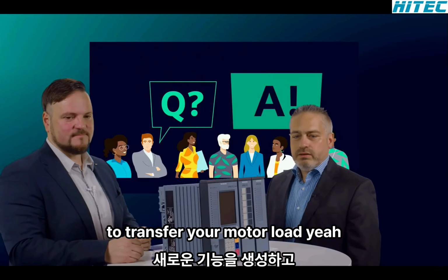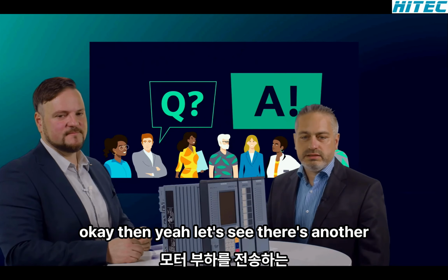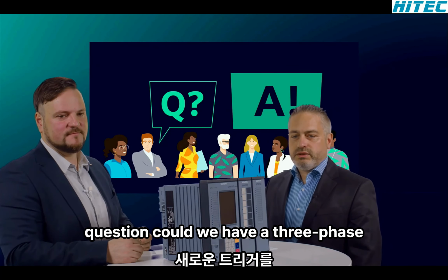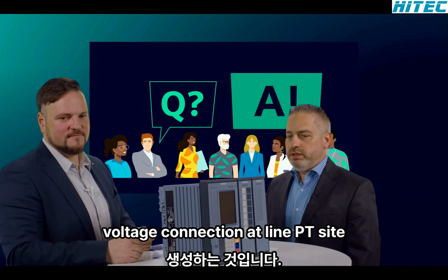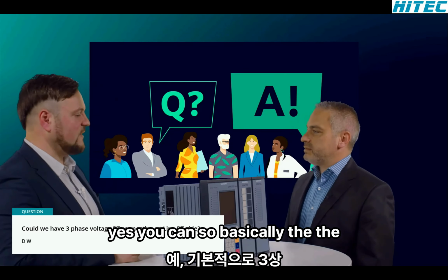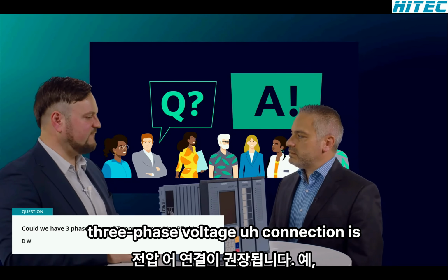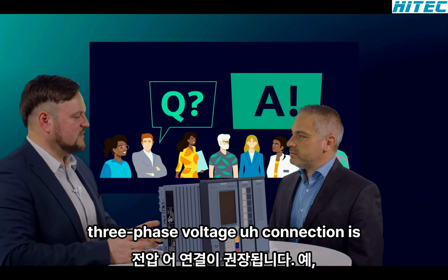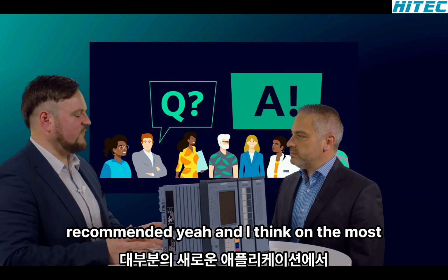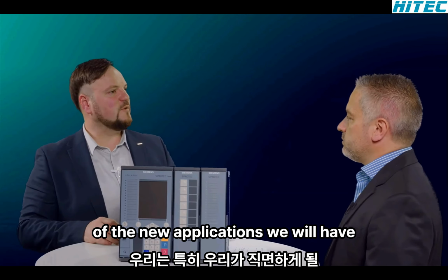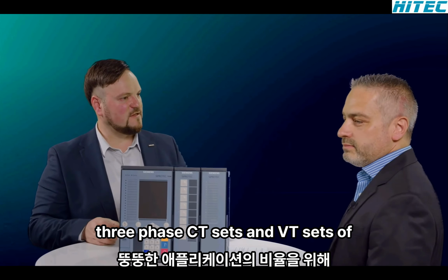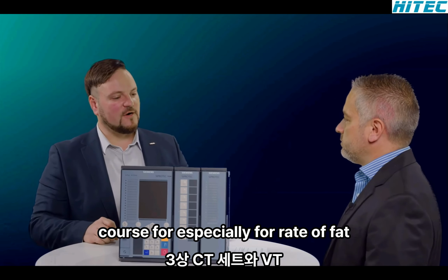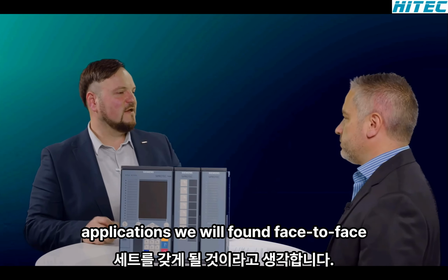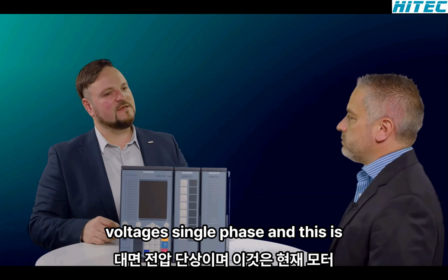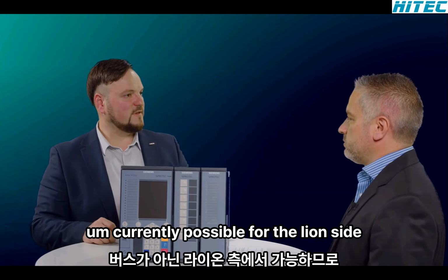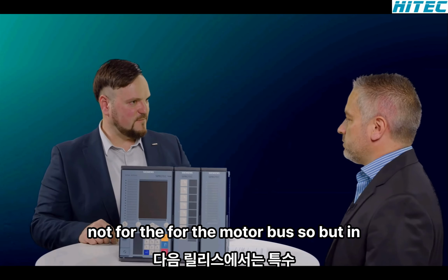Okay. Then, let's see, there's another question. Could we have three-phase voltage PT connection at the line PT side? Yes, you can. Basically, the three-phase voltage connection is recommended. And I think in most of the new applications, we will have three-phase CT sets and VT sets, of course. Especially for retrofit applications, we will find phase-to-phase voltages, single phase. And this is currently possible for the line side, not for the motor bus.